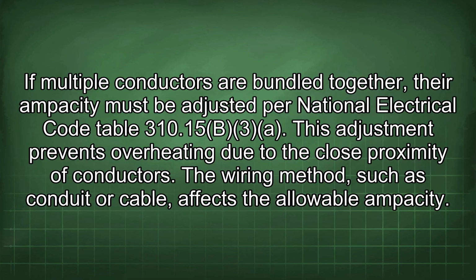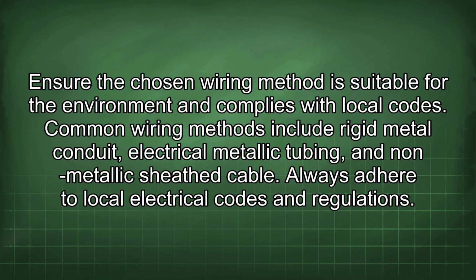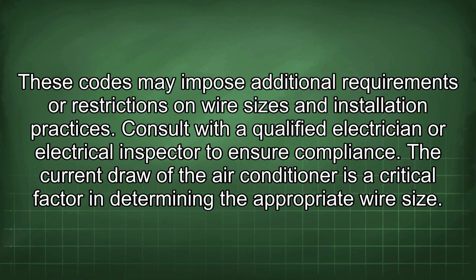The wiring method, such as conduit or cable, affects the allowable ampacity. Ensure the chosen wiring method is suitable for the environment and complies with local codes. Common wiring methods include rigid metal conduit, electrical metallic tubing, and non-metallic sheath cable. Always adhere to local electrical codes and regulations. These codes may impose additional requirements or restrictions on wire sizes and installation practices. Consult with a qualified electrician or electrical inspector to ensure compliance.